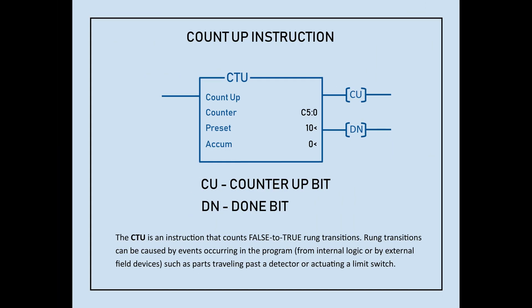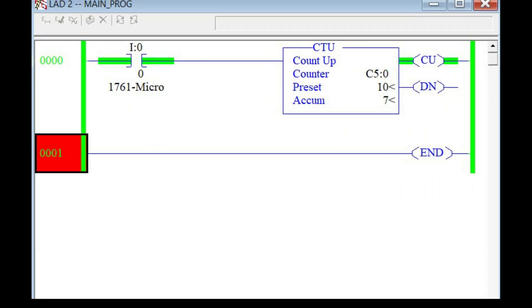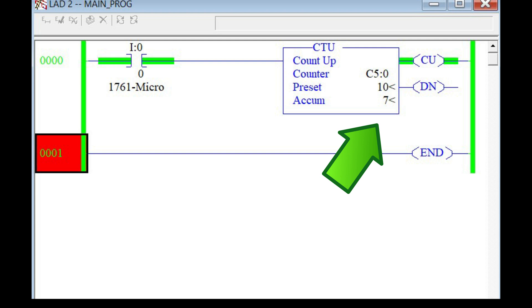The counter up instruction or CTU is used to count an event which happens logically or externally, and places that value in the counter's accumulator. The accumulated value is maintained even during false rung conditions, and can only be reset back to zero by the reset command.